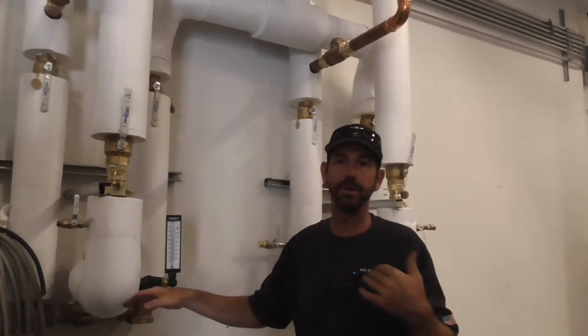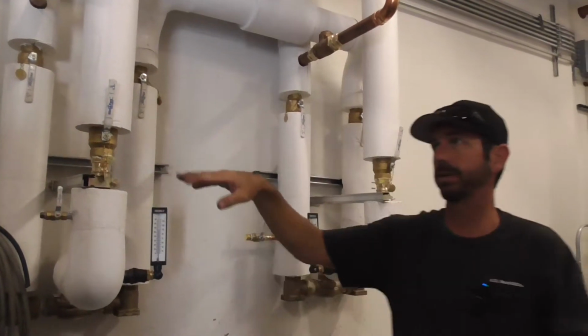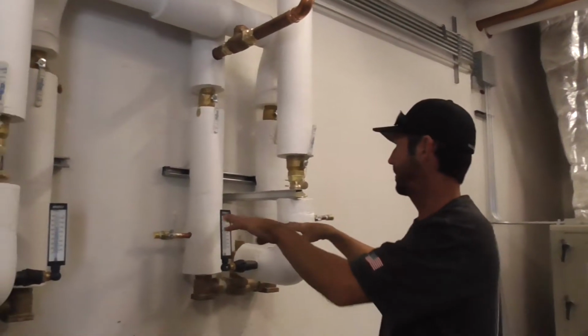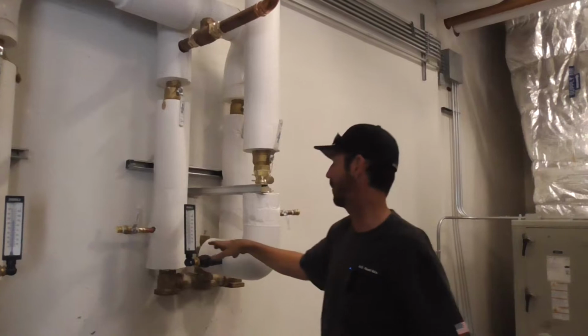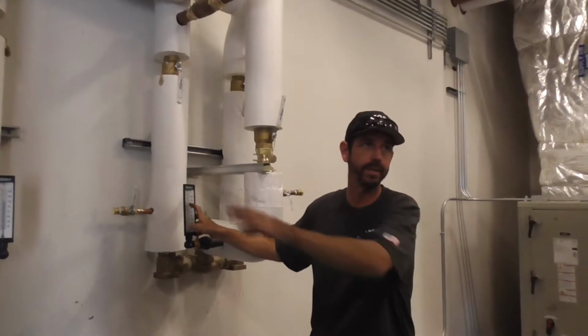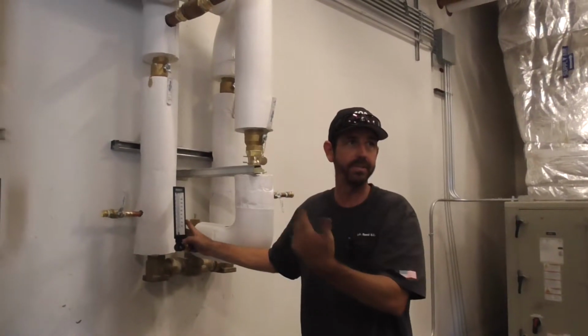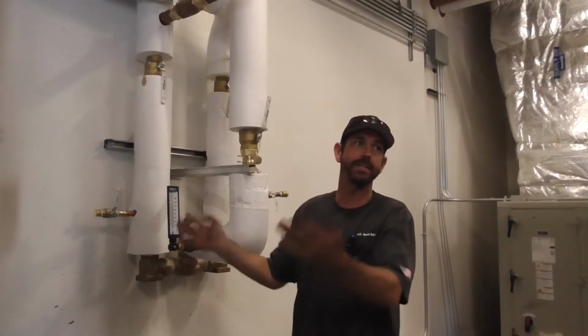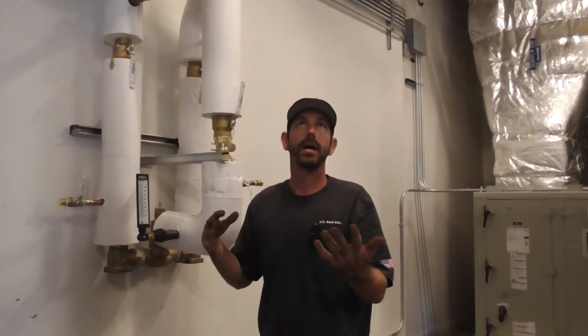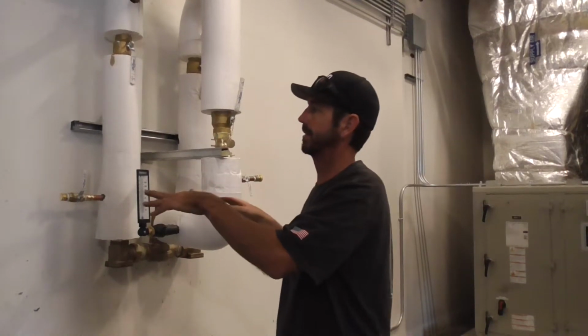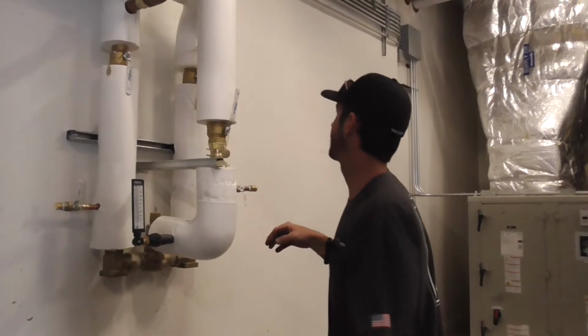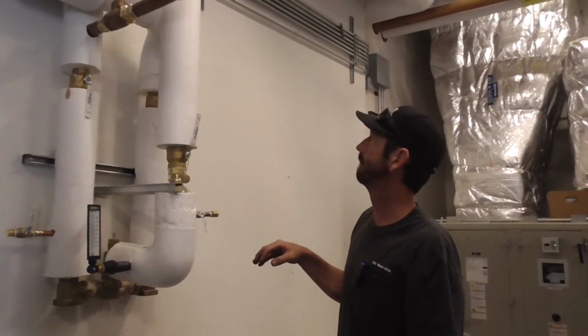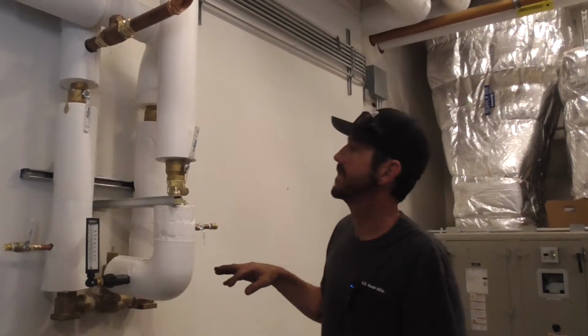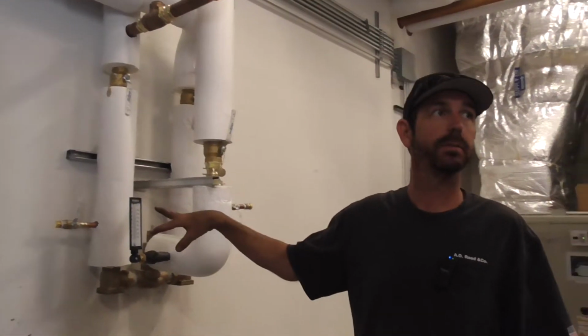Just depending on the flow through the building and if the circulating pump is running or not, the temperatures might be a little bit different. Like right now, we have a little bit more flow through this unit than that unit, okay? But they're both set up for 118. So as the building's capacity increases, it will flow water through both systems, right? Any questions on mixing valves?